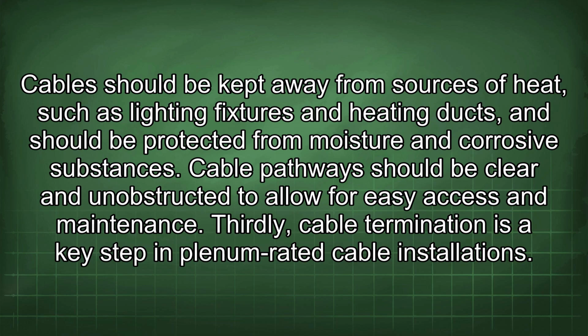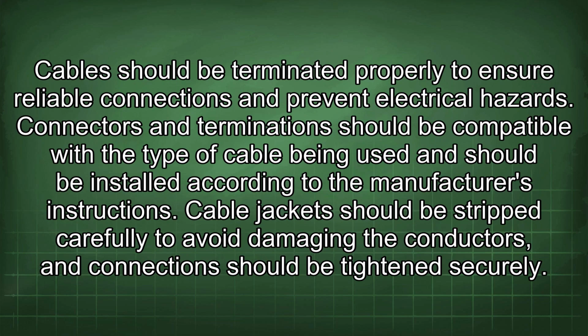Thirdly, cable termination is a key step in plenum-rated cable installations. Cables should be terminated properly to ensure reliable connections and prevent electrical hazards. Connectors and terminations should be compatible with the type of cable being used and should be installed according to the manufacturer's instructions. Cable jackets should be stripped carefully to avoid damaging the conductors, and connections should be tightened securely.